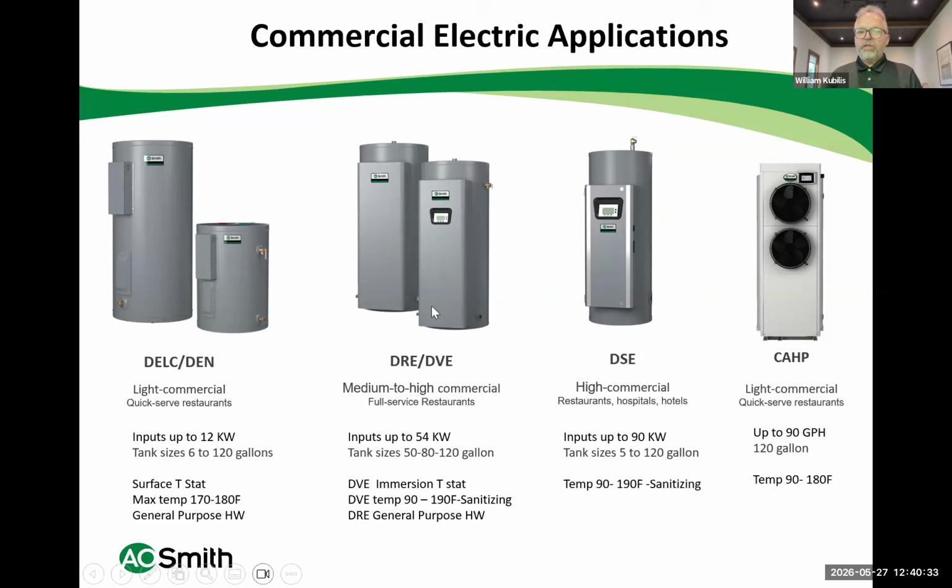We do have 2 units up here showing they're very similar. However, one has a screen on it. The one that has a screen on it is an immersion type thermostat. The probe is right in the water, sensing the water temperature in the tank. Whereas the model without the screen uses surface mounted thermostats that measure the outer tank.